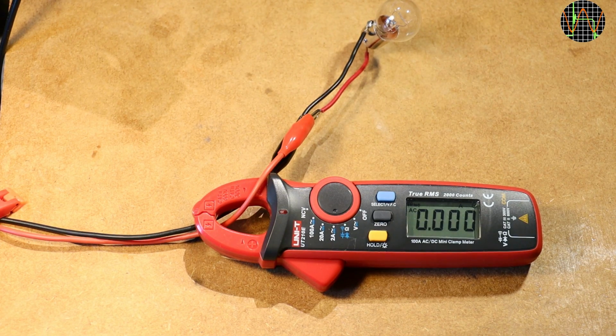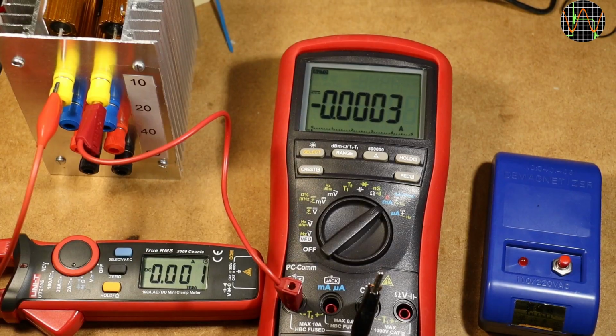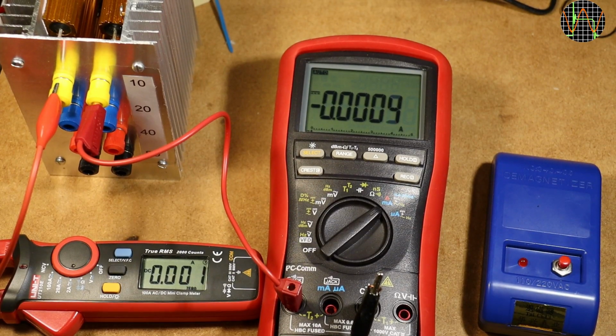This is about recalibrating it. I recently noticed that its current readings were way off. The spec says 2% for DC and 3% for AC, but this is more like 2% under reading and needs fixing. By the way, the problem is only on currents. Volts and resistance ranges are absolutely fine. As you can see, the zeroed meter reads 980 milliamps instead of about 1 amp.